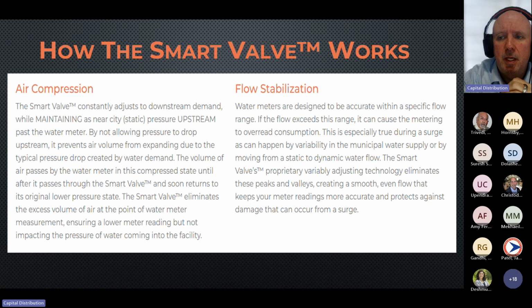And when you get a high demand, that meter can go into a range that's outside of its design, and it's going to overspin. And when it overspins, it's going to overspin in the direction that, as an owner, you don't want it to. It's going to charge you more. On top of that, when you get a pressure drop at the meter, you're inviting any pockets of air that are present in the line to expand. And when they expand and pass through the meter, it's going to be counted as volume.